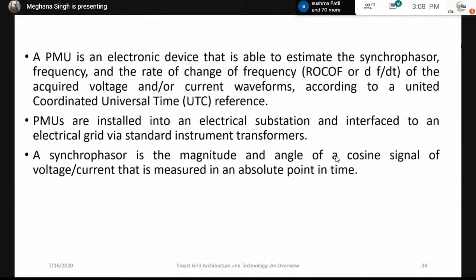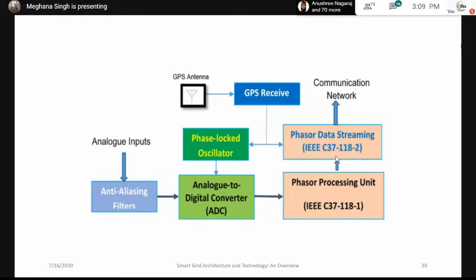So we have analog inputs passed through a low pass filter, also called an anti-aliasing filter, to remove unwanted components, then given to the ADC and on to the phasor processing unit. There is a phase lock oscillator for locking certain frequencies, a GPS antenna and GPS receiver feeding the phasor data streaming, which follows the IEEE 37.118 standard for communication networks. So: get the inputs, pre-process them, convert with the ADC, process as phasors, stream it, and give it to the communication network.